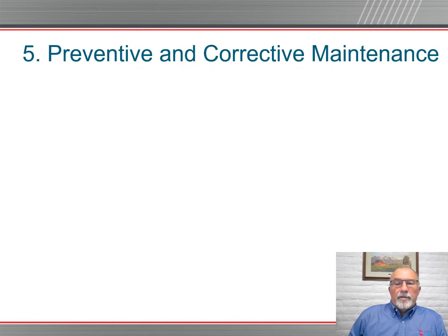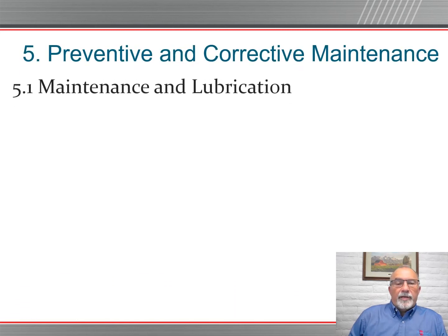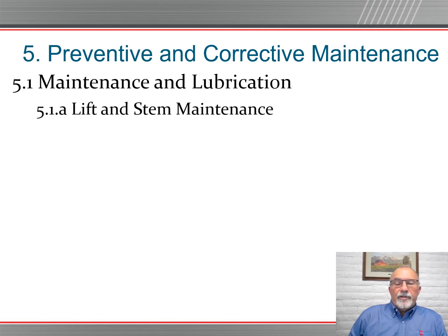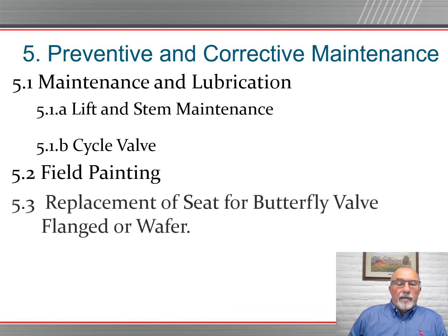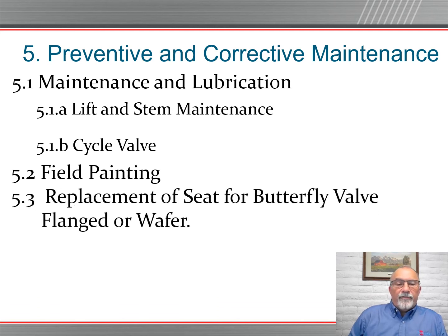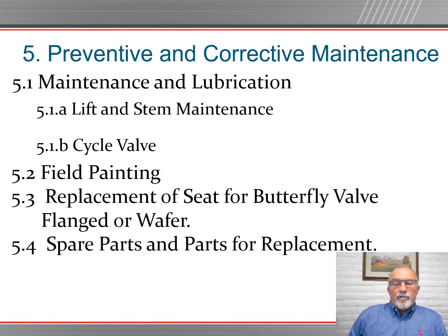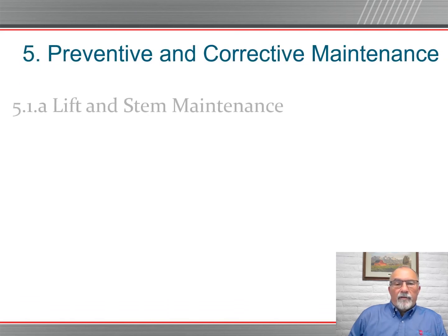Proper maintenance. Preventative and corrective maintenance: maintenance and lubrication, lift and stem maintenance, cycling the valve, field painting, replacement of seat for butterfly valve flanged or wafer, and spare parts and parts for replacement. These will all be covered now.